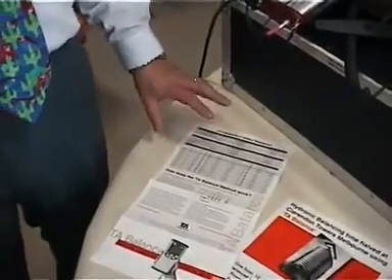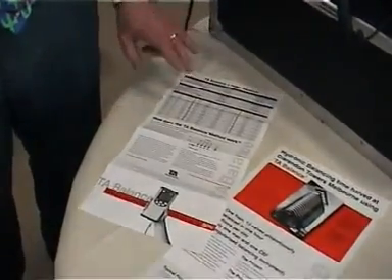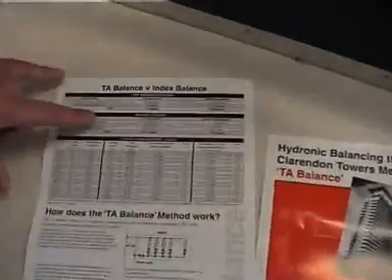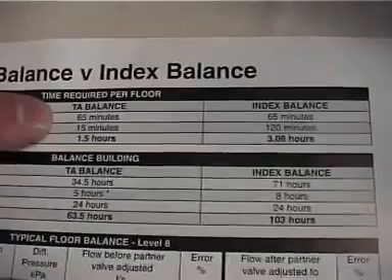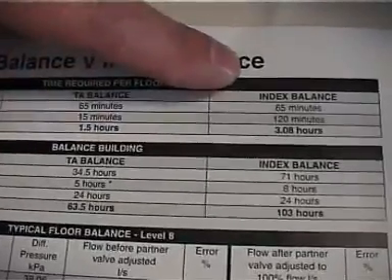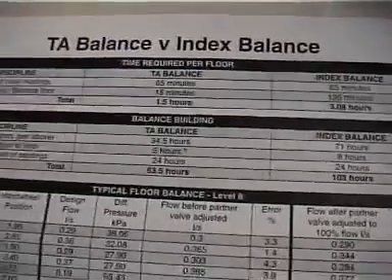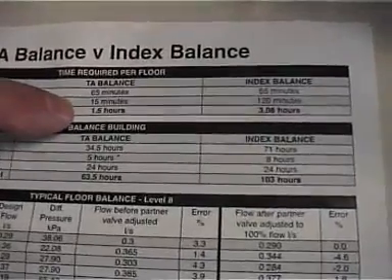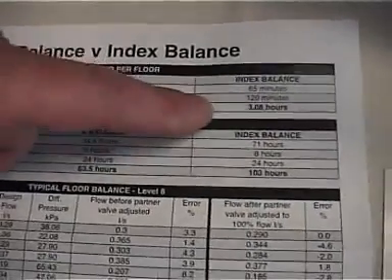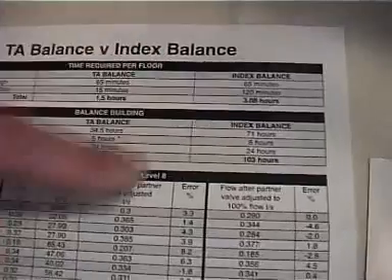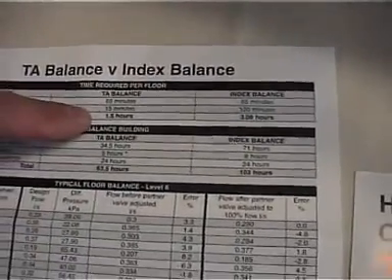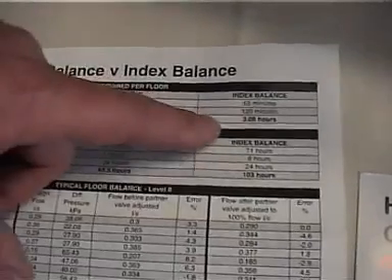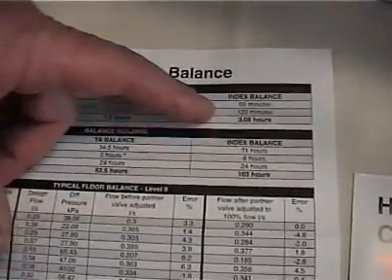TA CBI saves time, saves money and improves on accuracy when you're doing a hydronic balance. Typically, a balance time took 65 minutes per floor doing a TA balance, took the same time doing an index balance. The time saved when you're setting and balancing the floor on a TA balance method was 15 minutes, on an index balance method was 120 minutes. Consequently, the total hours was 1.5 hours on a balance system and 3.08 hours on an index balance system.